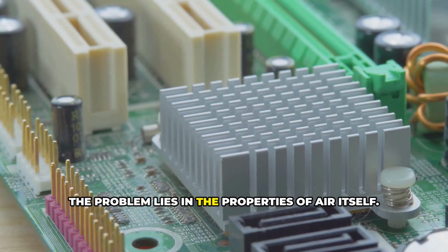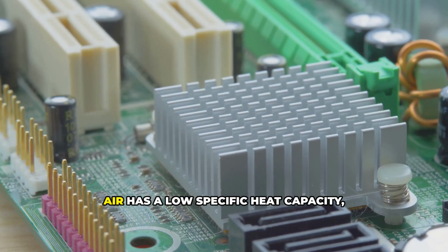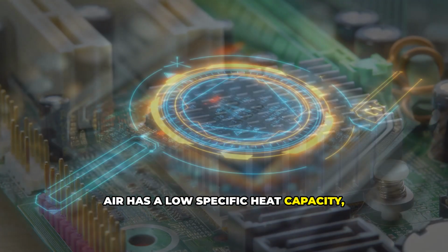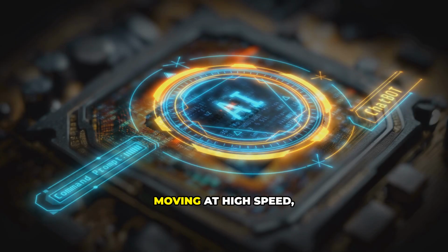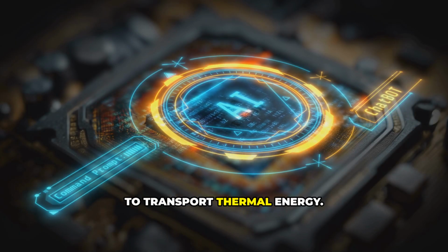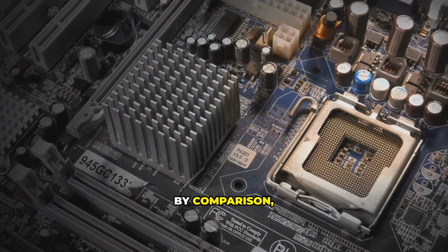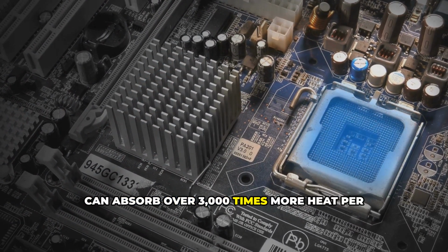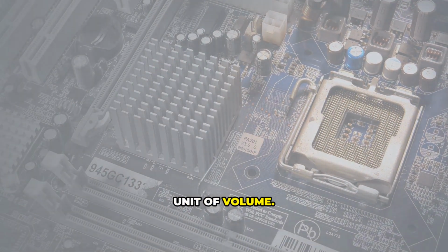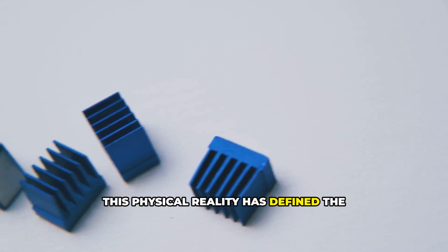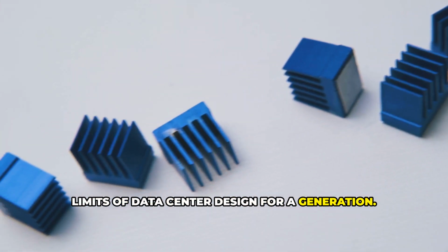The problem lies in the properties of air itself. Air has a low specific heat capacity, meaning it takes a tremendous volume of it, moving at high speed, to transport thermal energy. Water, by comparison, can absorb over 3,000 times more heat per unit of volume. This physical reality has defined the limits of data center design for a generation.